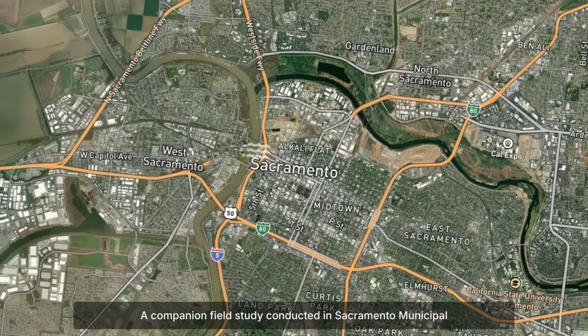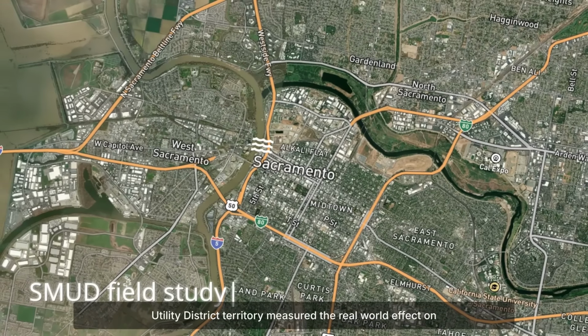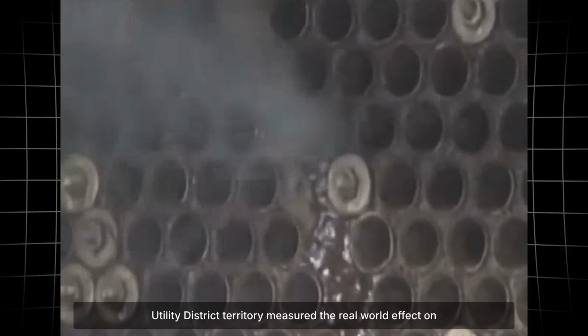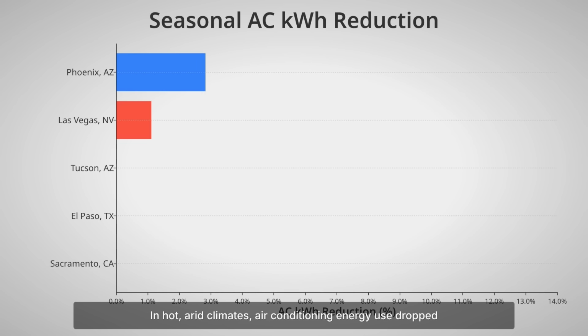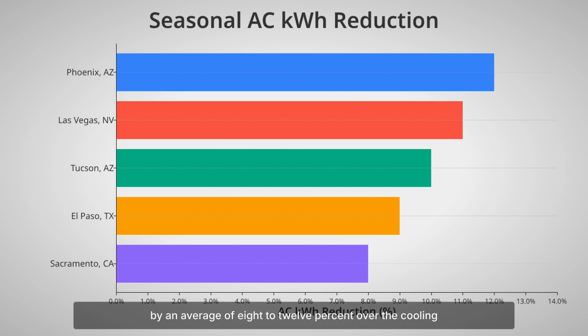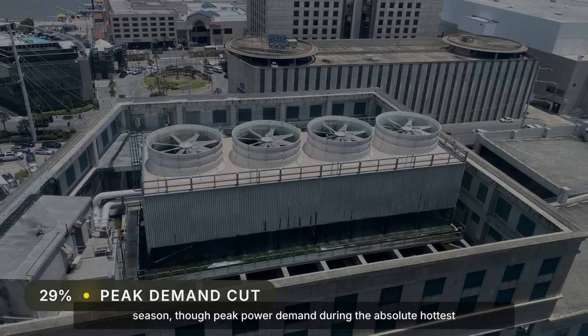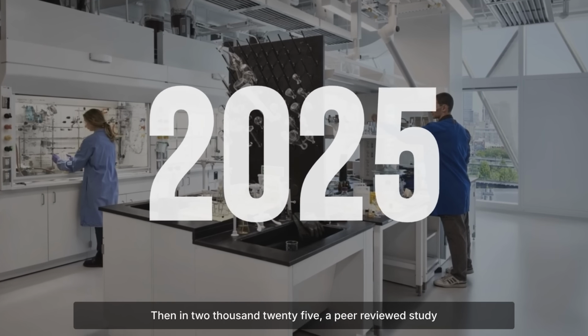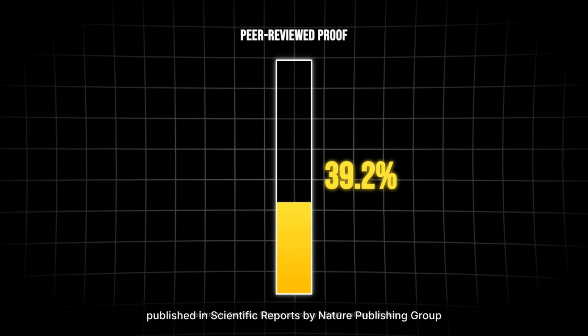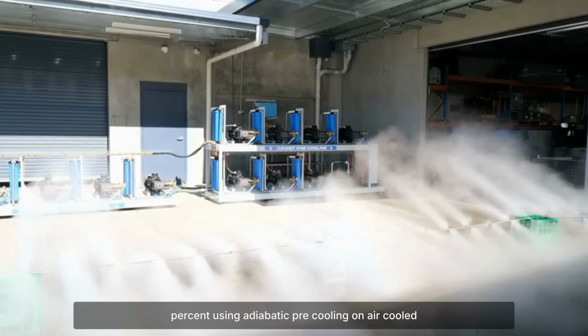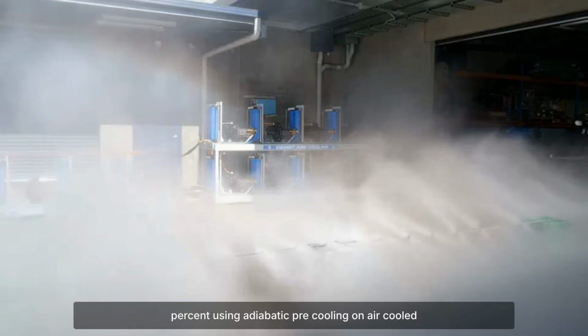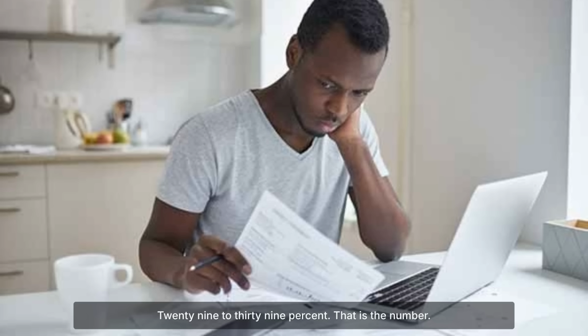A companion field study conducted in Sacramento Municipal Utility District territory measured the real-world effect on actual homes. In hot, arid climates, air conditioning energy use dropped by an average of 8 to 12% over the cooling season, though peak power demand during the absolute hottest hours fell by up to 23 to 29%. Then in 2025, a peer-reviewed study published in Scientific Reports by Nature Publishing Group documented average energy savings of 39.2% using adiabatic pre-cooling on air-cooled condensers, 29 to 39%.